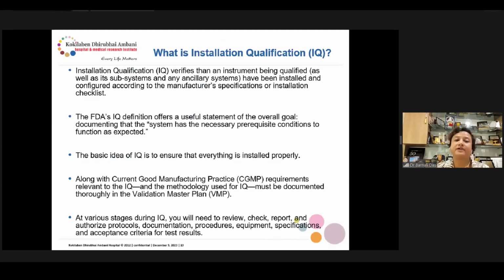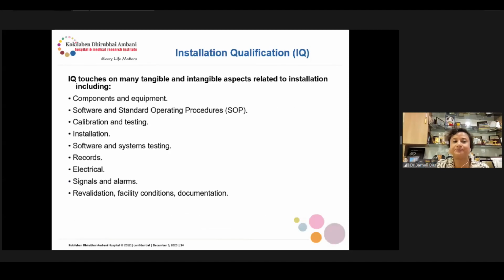So IQ verifies that the instrument being qualified, as well as subsystems and ancillary systems, have been installed and configured according to the manufacturer specification or installation checklist. The FDA's IQ definition offers a useful statement of the overall goal: documenting that the system has the necessary prerequisite conditions to function as expected. So this comes along with the current good manufacturing practice, CGMP, requirements.